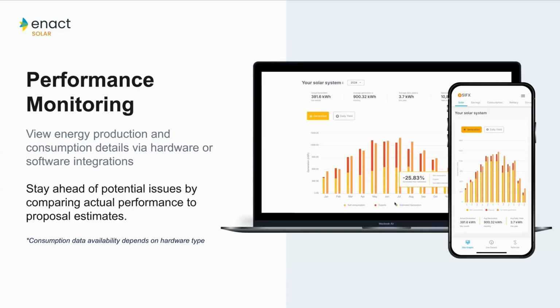And then the cool thing is month over month, we can see what actually is happening and how that compares to our estimates. In this case, a lot of the months it's very close. Some months are a little more, some months are a little less. This example is generally within that threshold, which is acceptable given some of the natural variations in weather or consumption. But if something isn't right, you can start to see some trends here. Maybe over the course of a few different years, there's shading and a tree growing, and you can start to see some of those patterns.